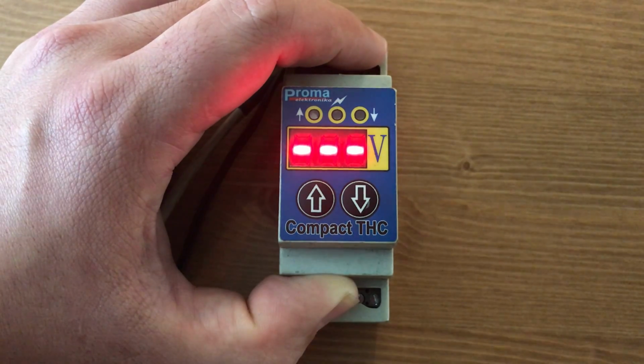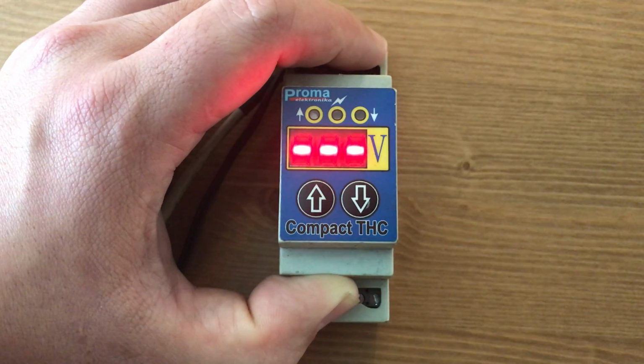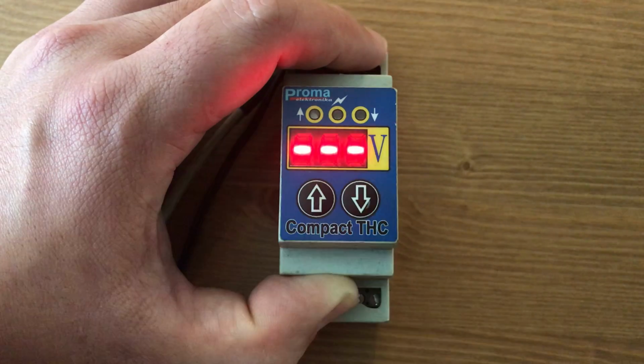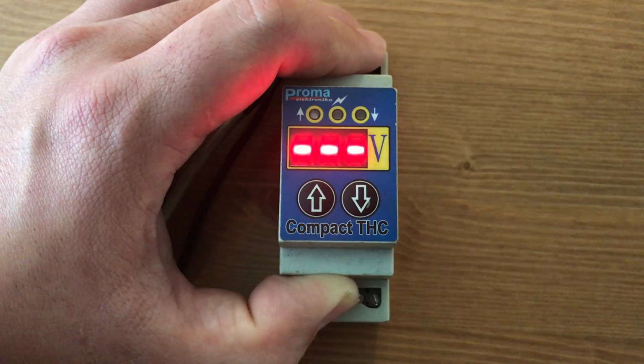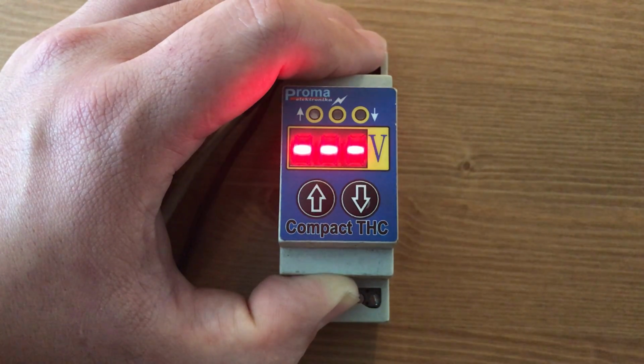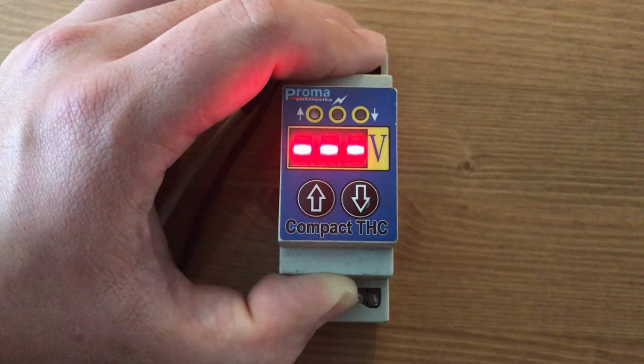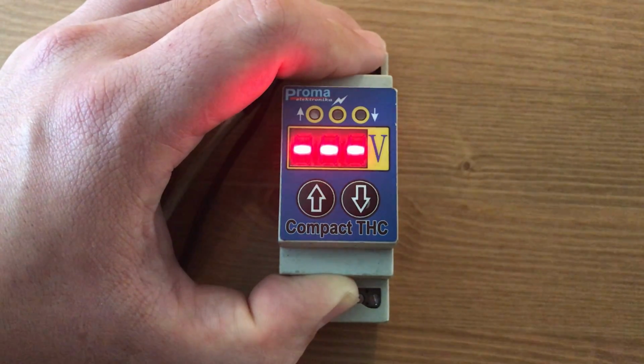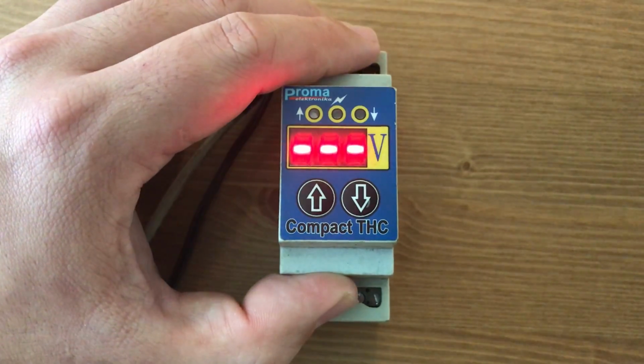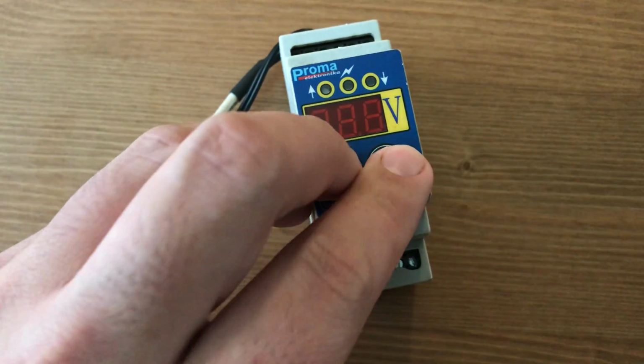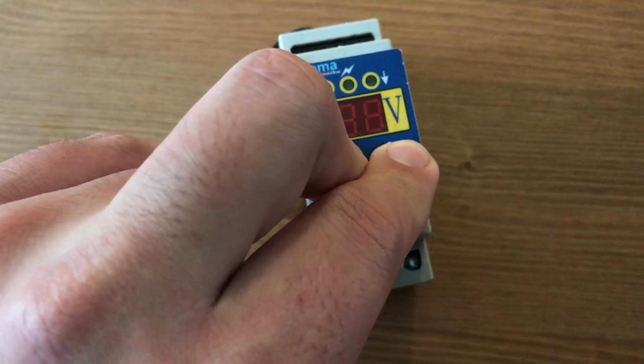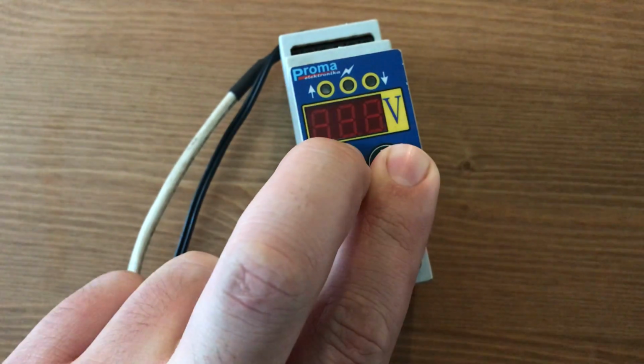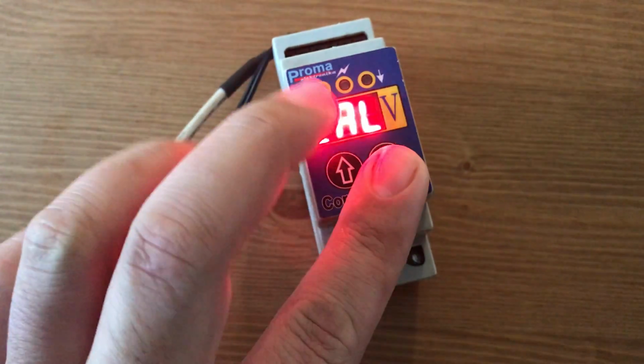The first thing we're going to do is turn it off, and then turn it back on while holding down these 2 buttons. We'll see the word CAL appear across the screen, and then we're going to release once we see CAL, and that will bring us to the calibration screen where we can make some small adjustments. So let's go ahead and turn it off, hold down the 2 buttons, and turn it back on. All right, THC, 36, CAL, release.